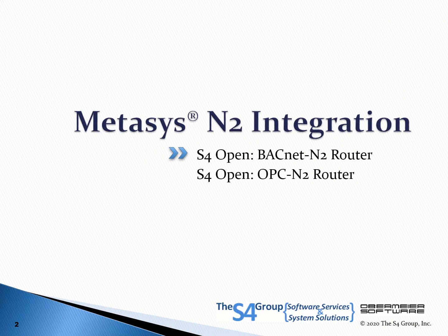Release 1.51 focuses on integration to the legacy proprietary Johnson Controls Metasys N2 building automation system. With the S4 Open BACnet-N2 router, everything that our configure wizard discovers on the N2 bus is emulated and published as BACnet IP devices and objects under a virtual BACnet network. The S4 Open OPC N2 router was not offered with Release 1.51, but will return in an incremental build for version 2.